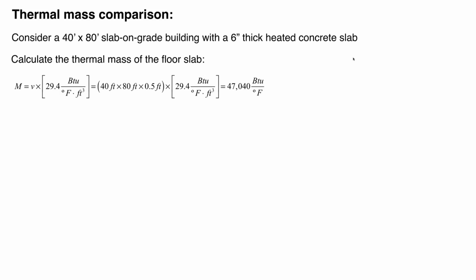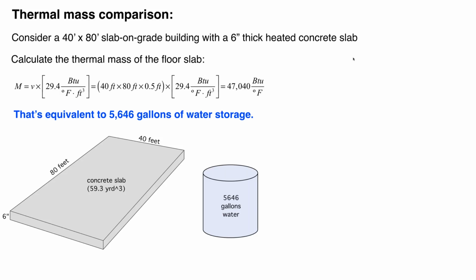So how does it compare to water? Well, here it is. That particular slab, if we compare it to the heat capacity of water, you need about 5,600 gallons of water to match the thermal storage ability of that slab. And obviously that's a pretty big ask.